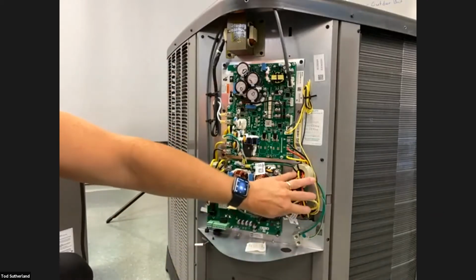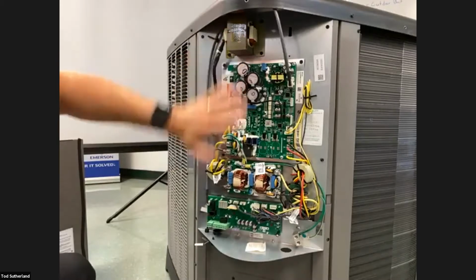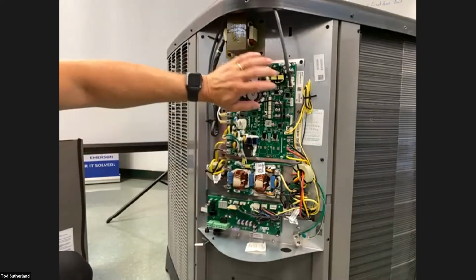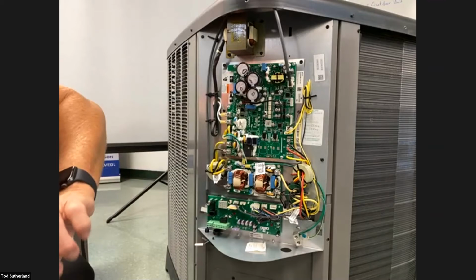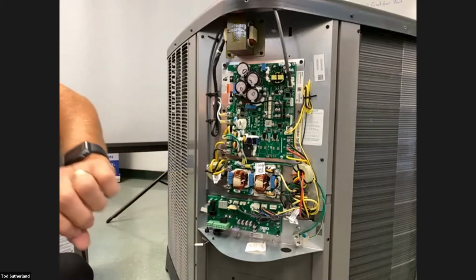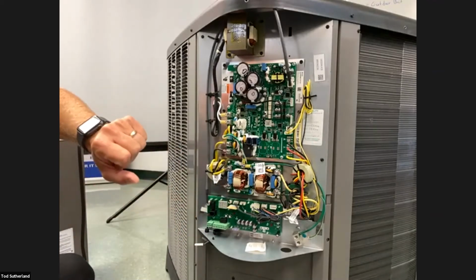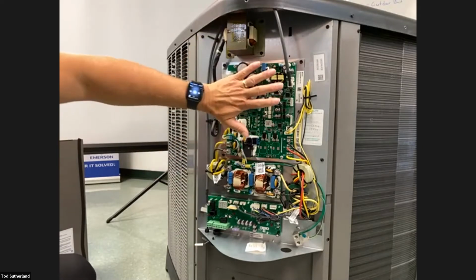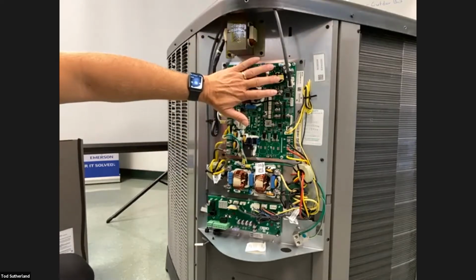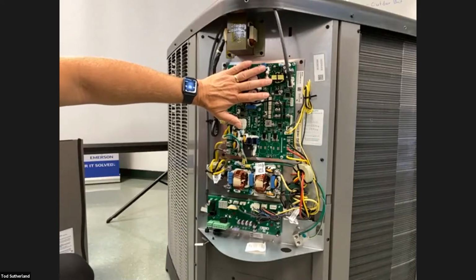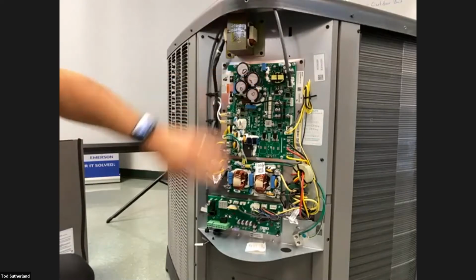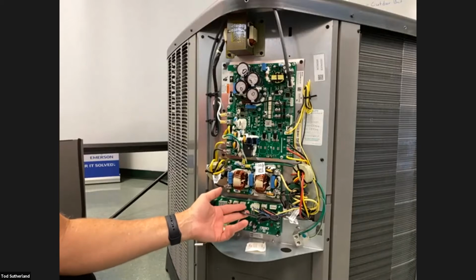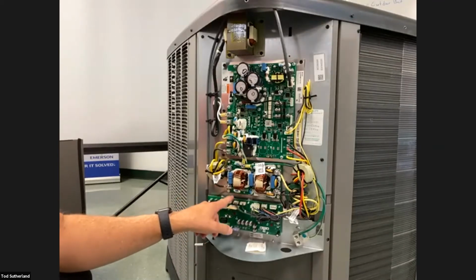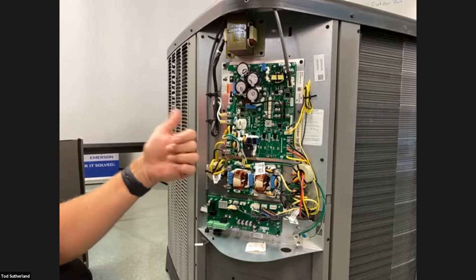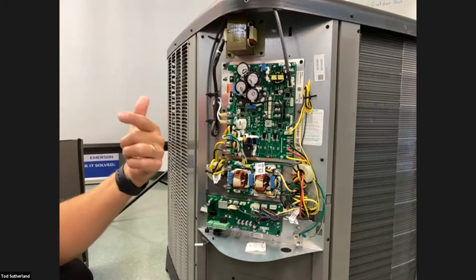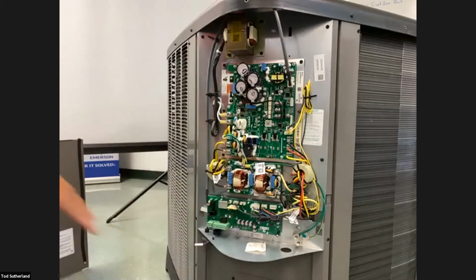Okay. So all these ferrite rings, the filter and the choke are all for cleaning up the voltage before we get to the board. So you're cleaning up the noise and the frequency, you're cleaning up the voltage, you're cleaning up the hertz, you're cleaning up everything so that we've got a nice, clean 230-volt signal going into the board. Okay. For testing some of this stuff, you'll notice all of your small black wires are all thermistors. They're all either suction line thermistors, low or ambient thermistors, or hot gas thermistors. They're all just sensing temperature.